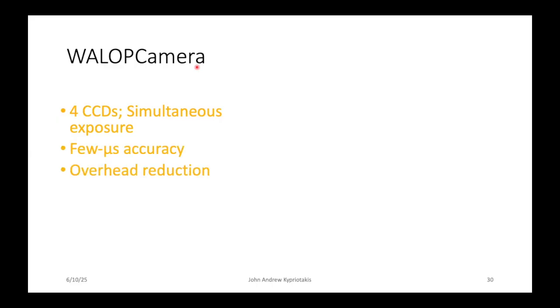The WALOP camera software is a dedicated software that will control all 4 CCDs simultaneously. So the problem is we have 4 CCDs and they need to start and end exposure at exactly the same time. And we cannot limit ourselves to the communication to the CCDs to have that happen. So we need a few microseconds of accuracy, and we need to also reduce the overhead. So while the CCDs are exposing or while the CCDs are saving the images, reading the CCDs, we need to be able to be doing other things with our telescope, slewing, for example.